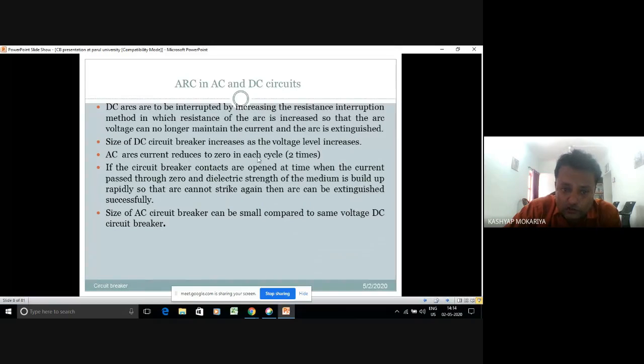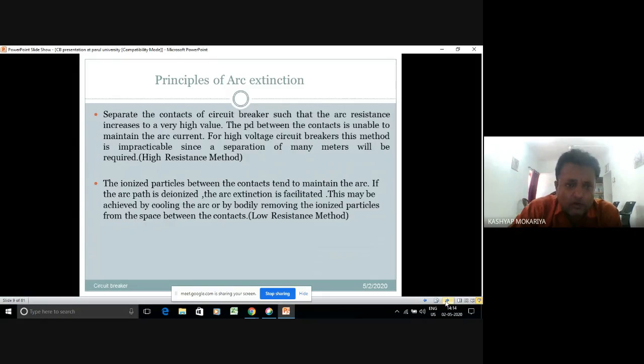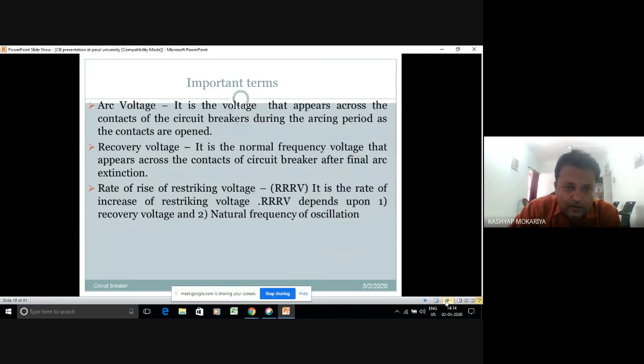An AC arc current reduces to zero in each cycle. If the circuit breaker contacts are opened at a time when the current passes through zero and the dielectric strength of the medium is built up, then the arc can be extinguished. So both have a different principle. I have just covered this high resistance and low resistance method here. These are the basic definitions. From the basics, I'll be switching towards the design and exit process during this presentation.